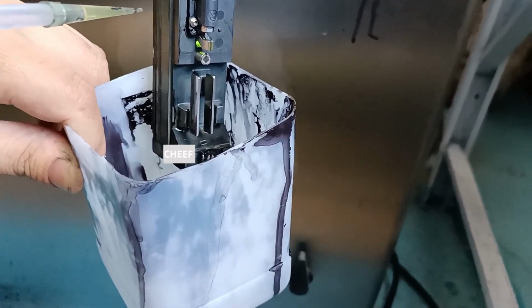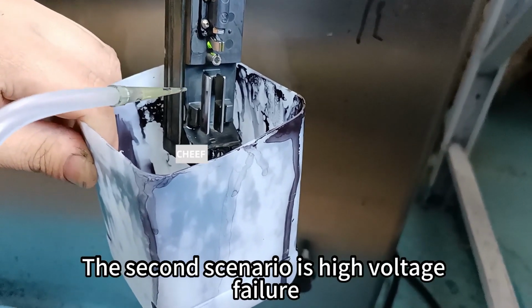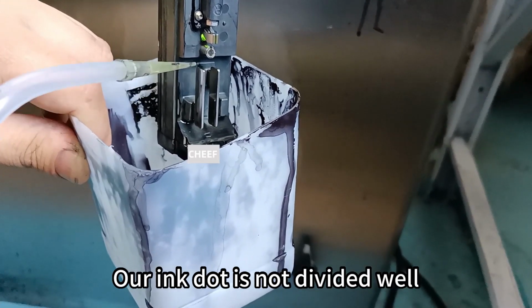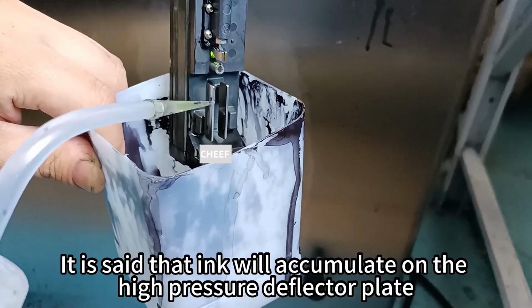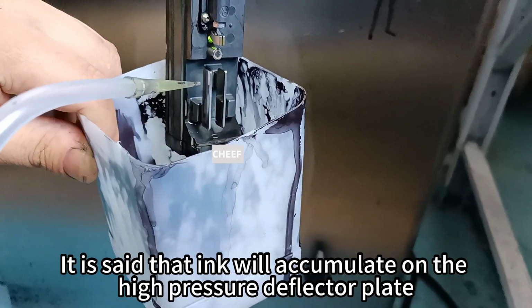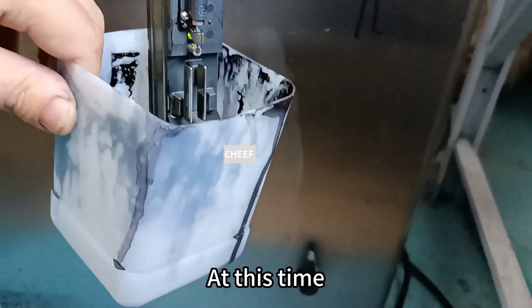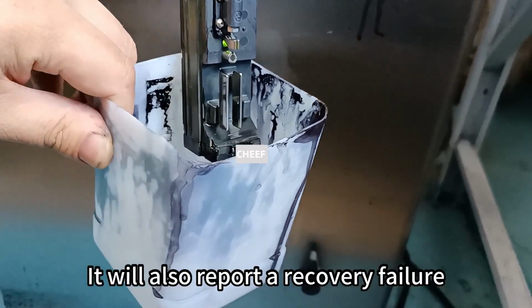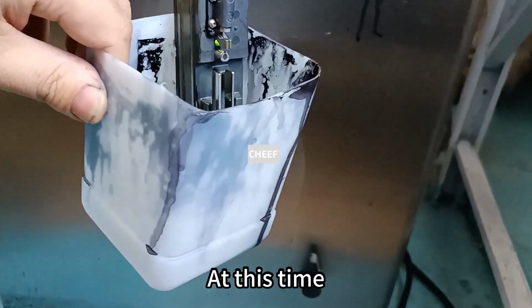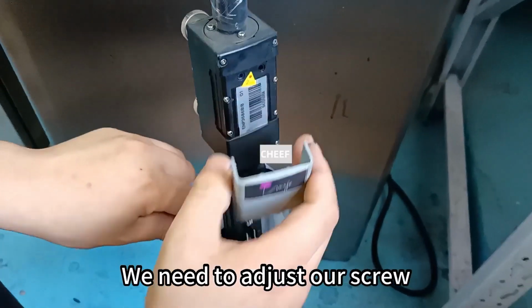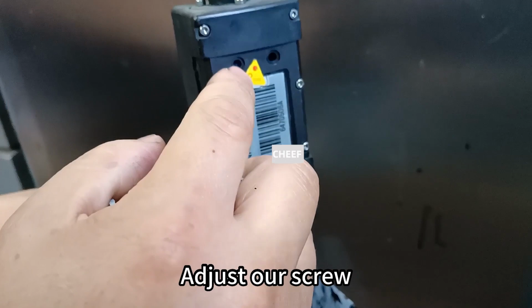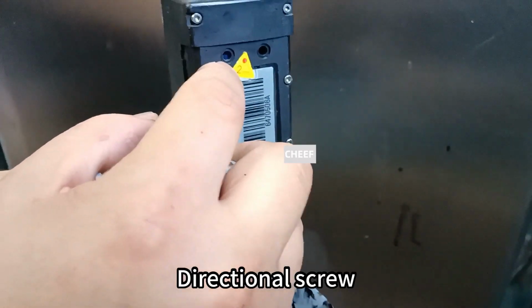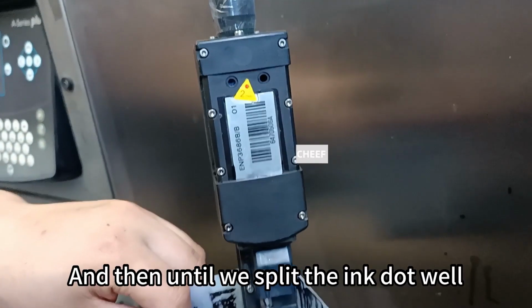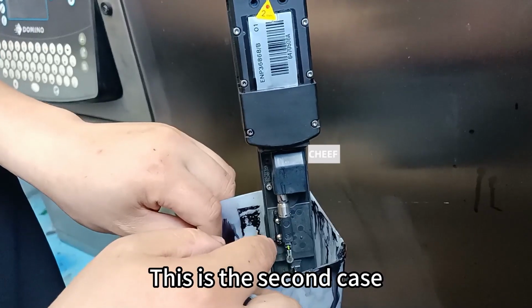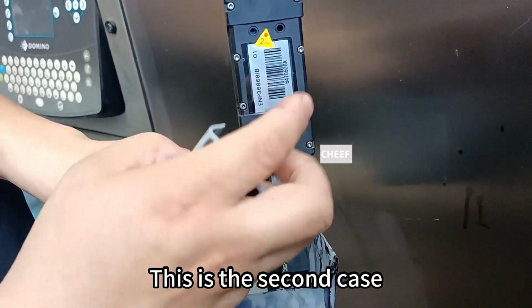The second scenario is high voltage failure when our ink dot is not divided well. Ink will accumulate on the high-pressure deflector plate. It will also report a recovery failure. At this time, we need to adjust our directional screw until we split the ink dot well. This is the second case.